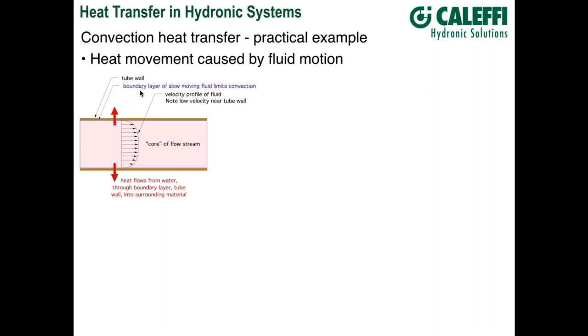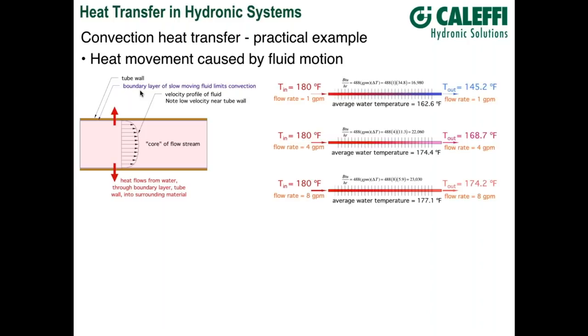The thicker the boundary layer, the lower the heat transfer coefficient. If the boundary layer can be made thinner, you get higher rates of heat transfer. For a given fluid and viscosity, what controls the thickness of the boundary layer is basically the speed. The faster the fluid moves through that tube, the thinner the boundary layer is, and hence the better the rate of heat transfer.